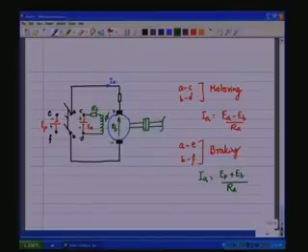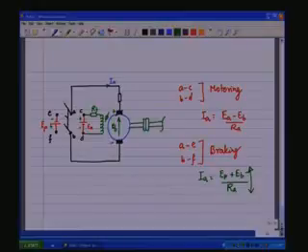Immediately it is going to change the direction. You are going to have a reverse current flowing, but it will be of pretty high value because RA is going to be small, whereas earlier it was the difference in voltage between the armature voltage and EB.